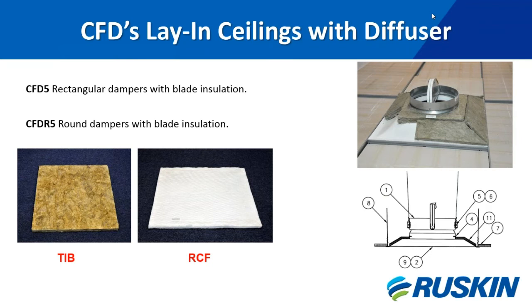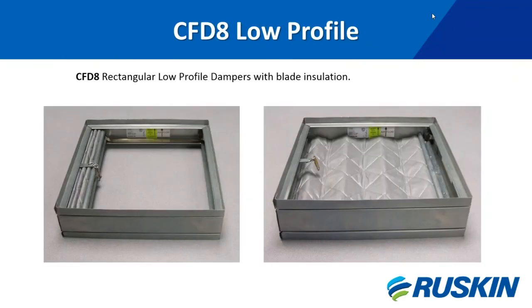Next is the CFD 5 for lay-in ceilings or diffusers with a smaller neck — the CFD 5 should be used. The CFD 5 or CFD R5 are supplied with a TIB (mineral wool thermal insulation blanket) or an RCF (refractory ceramic fiber thermal insulation blanket) that is used to cover the back side of the diffuser. Next is the CFD 8, which is a low-profile damper used just like the CFD 2 series but where space is restricted.